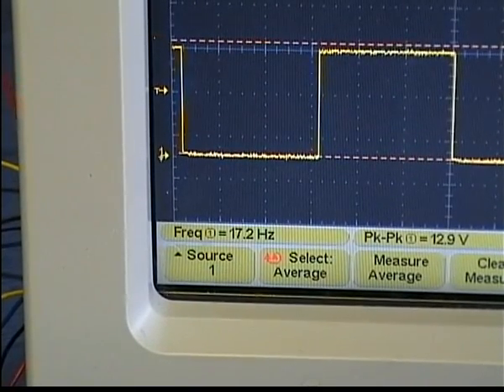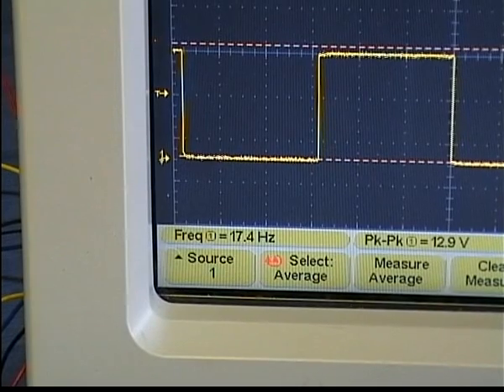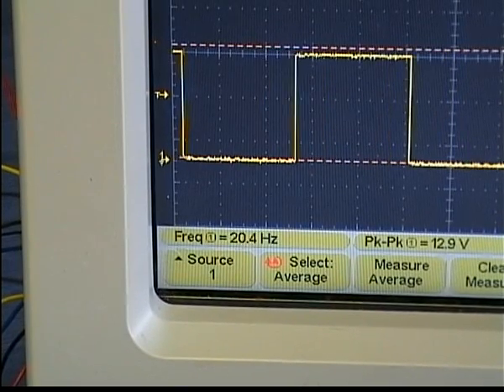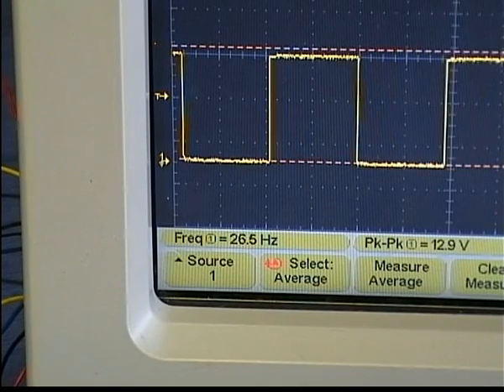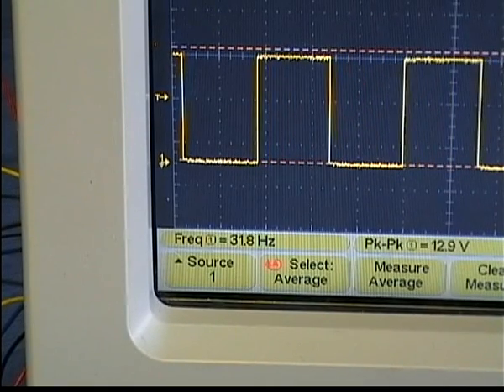You can see the frequency of the feedback pulses on the screen. The frequency is shown on the bottom left corner and can be converted into RPM by multiplying this number with the number 30.